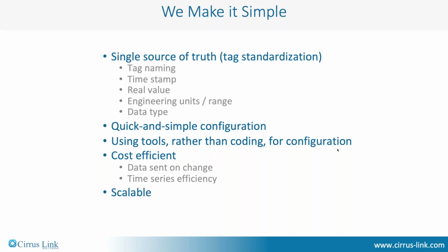What we mean there is that we've had 40 years or more of dealing with register value pairs. So we've got Modbus register 40,012, it's a value of 520. What is that? Is that a pressure? Is it a raw analog value? Has it already been scaled? What's the engineering units? What's engineering high, engineering low?